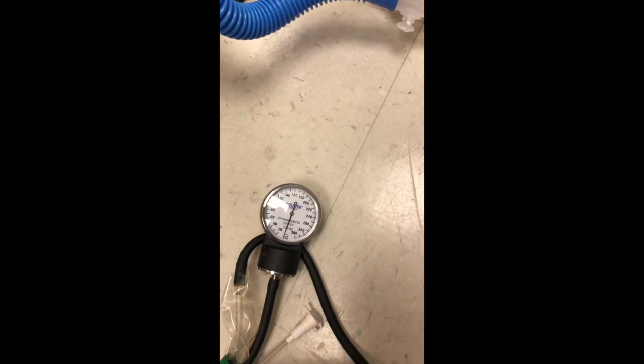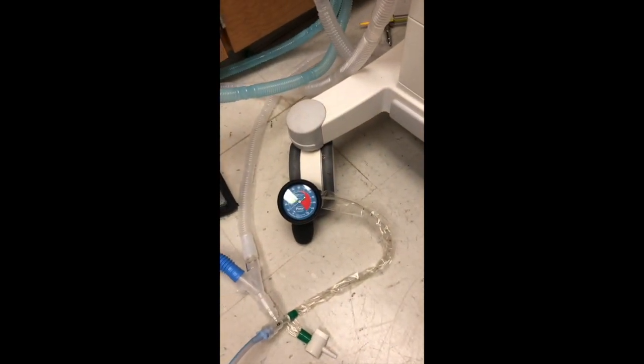So by keeping a higher peak pressure on the ventilator and adding resistance through the use of this valve, we can actually change pressure or volume individually with a single ventilator. And this is the key to ventilate multiple patients with a single ventilator. Also, there are some caveats, of course. This is no substitute for a single ventilator on each patient, and as I said, desperate times call for desperate measures. This may be useful when we are running out of ventilators and till we get other ventilators, or if we don't have any option.